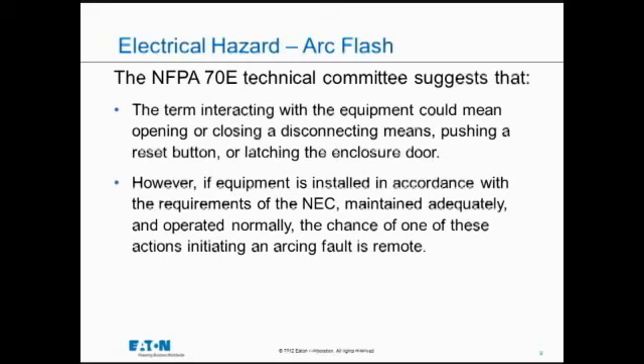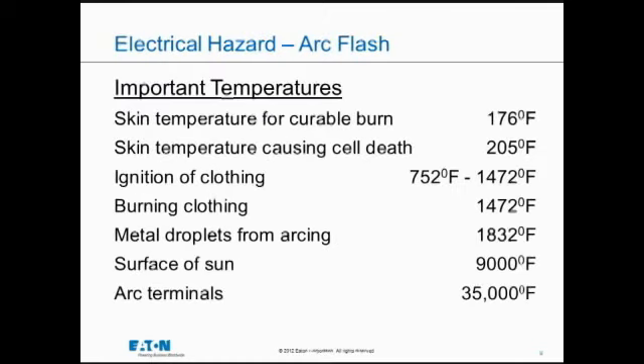So to protect ourselves as humans for the arc flash condition, it gets down to that bottom right-hand corner. That's the temperature that's coming at us. And the top numbers, the 205 degrees Fahrenheit, is more or less where we're in trouble. As humans, we're in trouble at 205, and you could convert that to Celsius if you wanted to. But there's a big mismatch between what's coming from the arc in terms of temperature and what we're capable of accepting as humans. And somewhere in the middle, there's clothing that's catching on fire and burning and igniting, and the temperatures associated with that are on this chart.